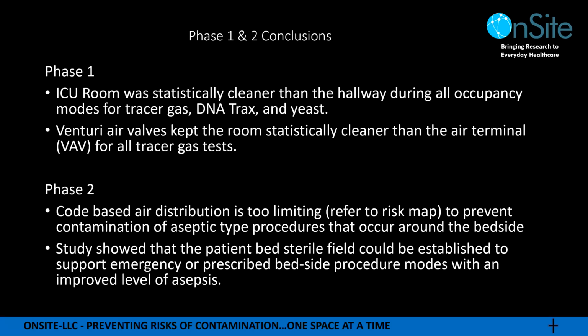In phase 2, what we found is that the code-based air distribution really limits and doesn't allow us to provide an aseptic space for a procedure to occur around the bed. And the study also showed that the patient bed sterile field could be made better to support emergency or prescribed bedside procedure modes with an improved level of asepsis.